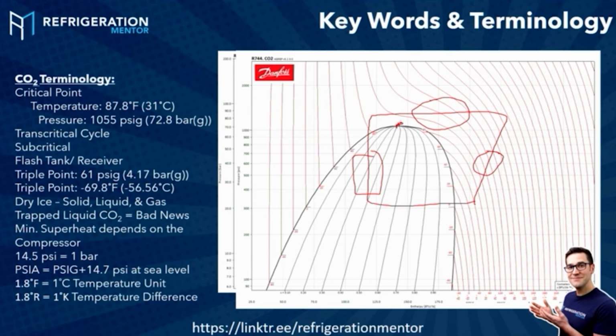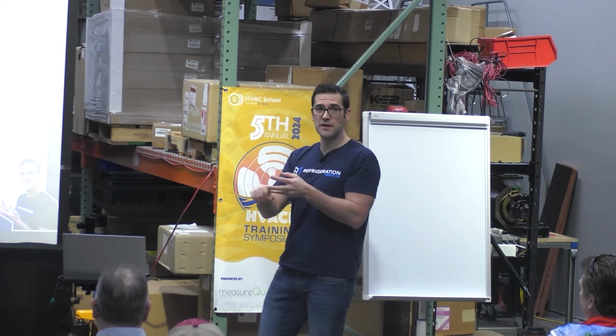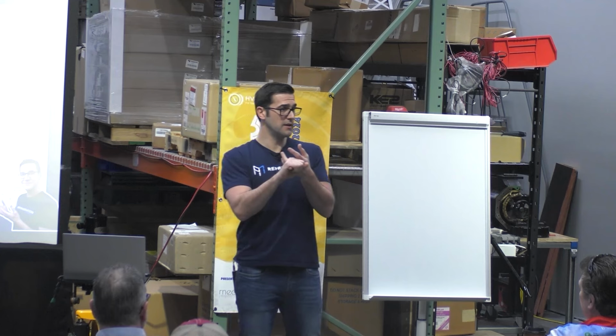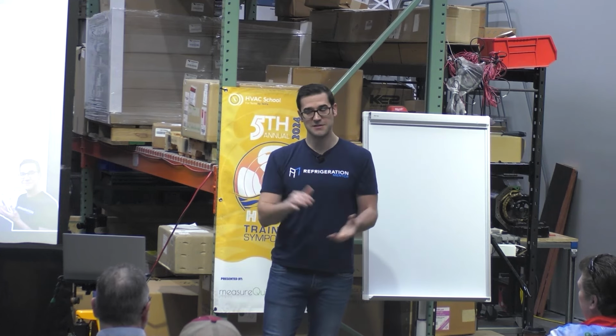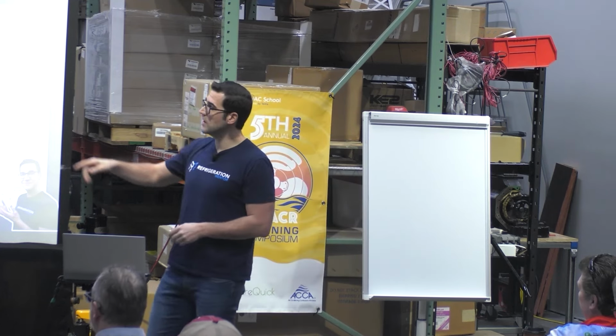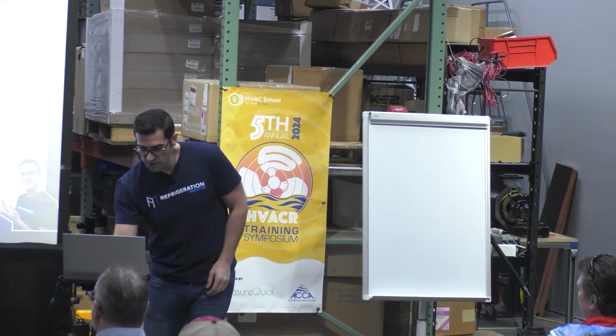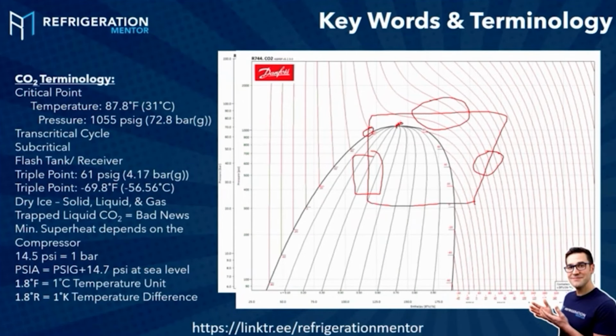So we take this fluid that comes down your drop leg. In air conditioning terms, you call that your liquid line. In refrigeration terms, it's your drop leg. Or some people call it, once again, condensation leg. There's lots of different terms. You've got to understand those terms. And then we go through this high pressure valve that's right here, we'll say. It drops the pressure down into this vessel. This vessel, some people call it vessel, tank, flash tank, receiver, it's a receiver. Okay? Now this is where your liquid is.